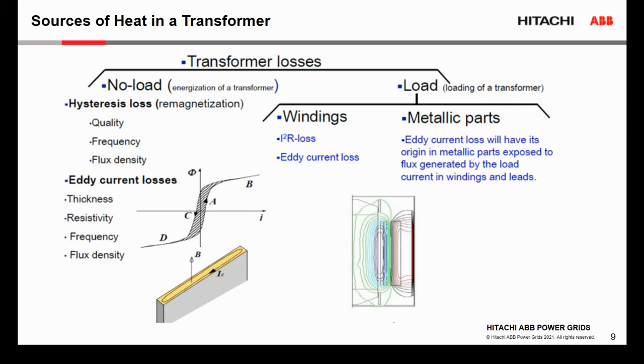So when we talk about the sources of heat in the transformer, we have two sources. First is the core, and in the core we have the no load losses. Every time we energize the transformer, it produces the no load losses, and the no load losses have two components. One is from the hysteresis, driven by the quality, frequency, and flux density of the core. Another is due to the eddy current circulating in the core sheets. If we want to reduce the core eddy current losses, we want to change the resistivity, the thickness, and the frequency. By changing those factors, we can reduce the eddy losses in the core as well.